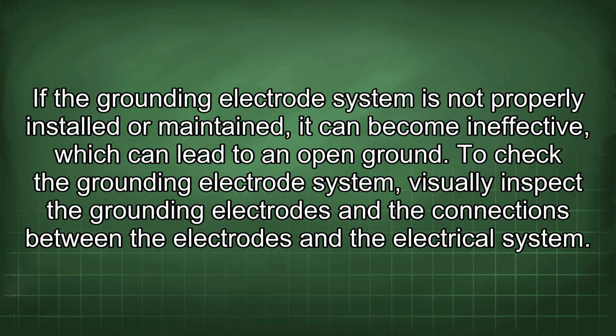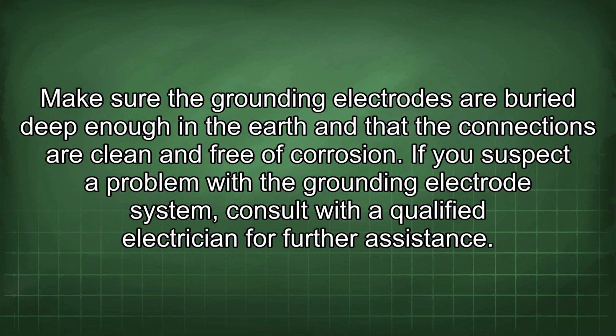If the grounding electrode system is not properly installed or maintained, it can become ineffective, which can lead to an open ground. To check the grounding electrode system, visually inspect the grounding electrodes and the connections between the electrodes and the electrical system. Make sure the grounding electrodes are buried deep enough in the earth and that the connections are clean and free of corrosion. If you suspect a problem with the grounding electrode system, consult with a qualified electrician for further assistance.